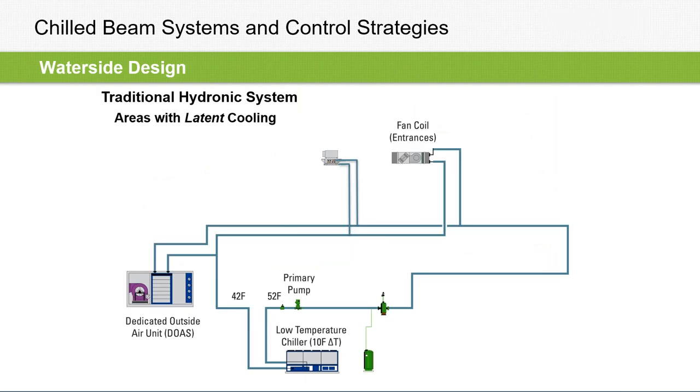So the last point we'll make here is at times there are scenarios where you do want to see a condensing chilled beam. We kind of talk about it's sensible only, but there are applications where you do want to condense. Maybe it's a cost-driven decision, and you don't want to temper the water. You just want to have that low temp water all throughout the building and save some piping costs. Maybe you need more heat capacity per foot of chilled beam. You're not quite meeting your loads, and you want to drop that.